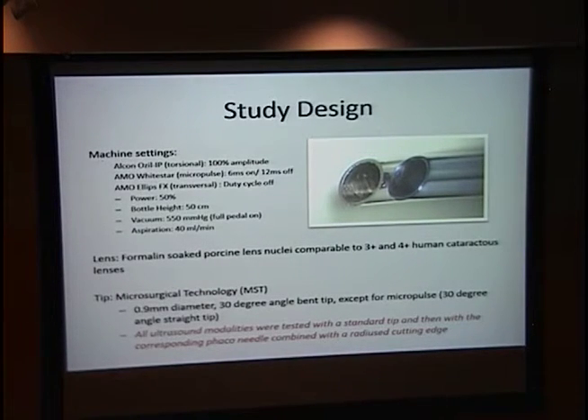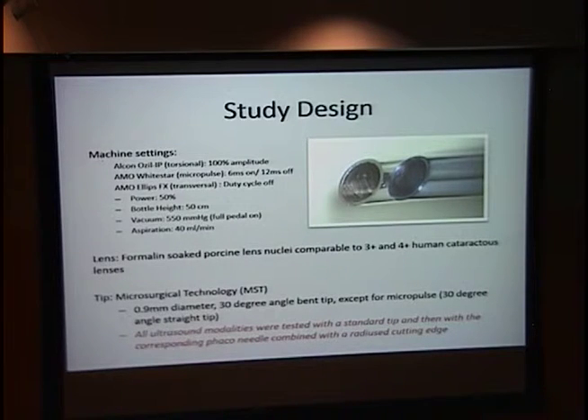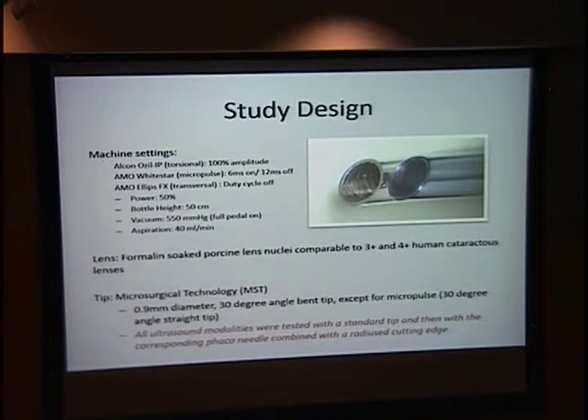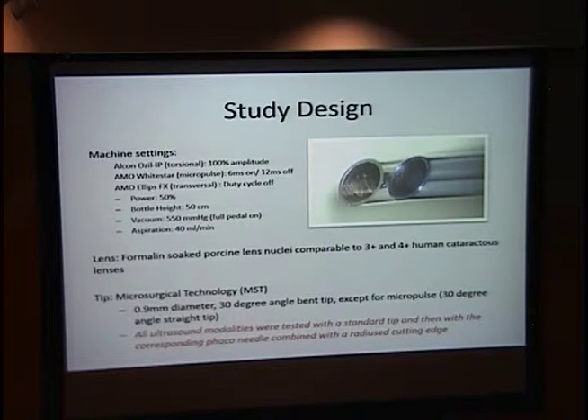Our study design has been used in a bunch of our studies looking at optimizing phacoemulsification. We used three different ultrasound modalities: the Alcon, which is a torsional ultrasound; the AMO WhiteStar, which is a micropulse; and the AMO Ellipse, which is a transversal modality. We used the same power, bottle height, vacuum, and aspiration to keep all parameters even between them. Our lenses are porcine lens nuclei that we order and soak in a 10% formalin solution to mimic human cataracts. We looked at two different types of lenses comparable to both a 3-plus and a 4-plus human cataract lens. The tips are all from MST; we use a 0.9 millimeter diameter — found to be the most efficient in previous studies — and a 30-degree angle bent tip, except for micropulse, which uses a straight tip. We then used them with their direct counterpart with a radius cutting edge.